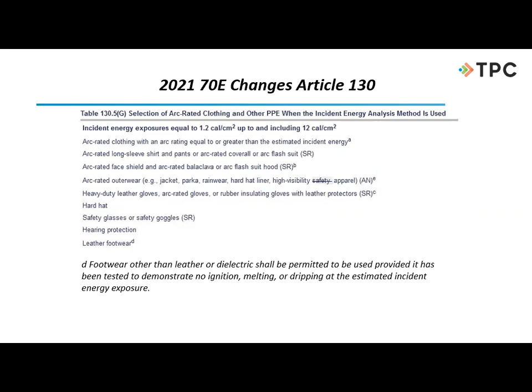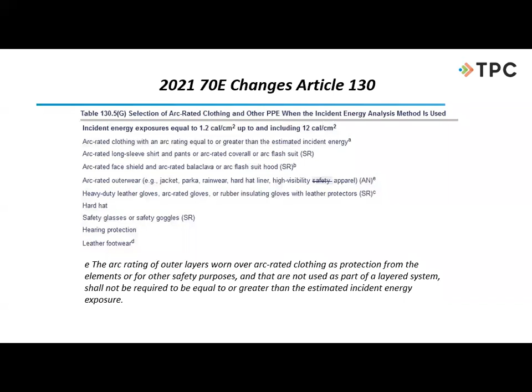Also, note E is telling us that maybe for some reason I have to wear a reflective vest. Maybe that's part of the requirements of the company I'm working for. And the reflective vest would have to have an arc rating on it, but it's just telling us that that reflective vest or that rain jacket or whatever other piece of apparel I'm going to put on does not have to be equal to or greater than the estimated incident energy, as long as it's worn over my arc rated clothing that is equal to or greater than the calories per centimeter squared. So a couple new notes there for the incident energy analysis method.